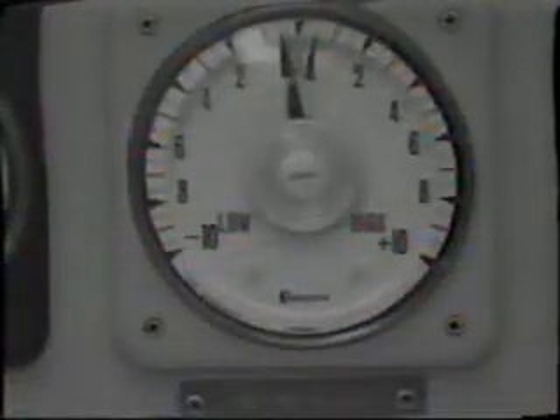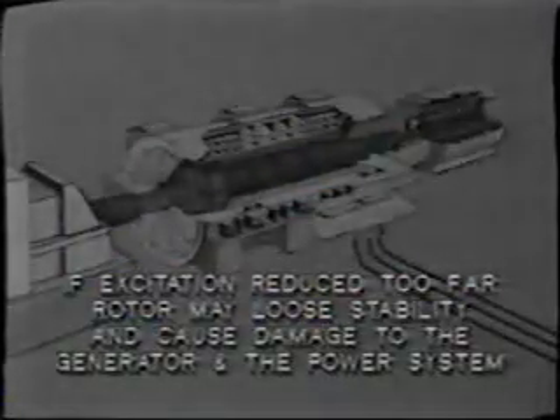Upsets or variations on the power system could seriously affect the excitation of the generator. A typical example is when voltage is very high on the system. This could be due to the capacitive effect of lightly loaded long transmission lines or high voltage cables. In order to reduce this voltage, the generator voltage regulator will reduce the excitation current circulating through the rotor winding. If this reduction in excitation is taken too far, the rotor may not have sufficient magnetic torque to remain in synchronism. It would lose stability and probably slip a pole and then another. This has a most damaging effect on the generator and on the power system itself. Indeed, minimum excitation is one of the limits of generator operation. Other limits are overheating of the stator winding due to overload, and overheating of the rotor winding due to excessive excitation current.